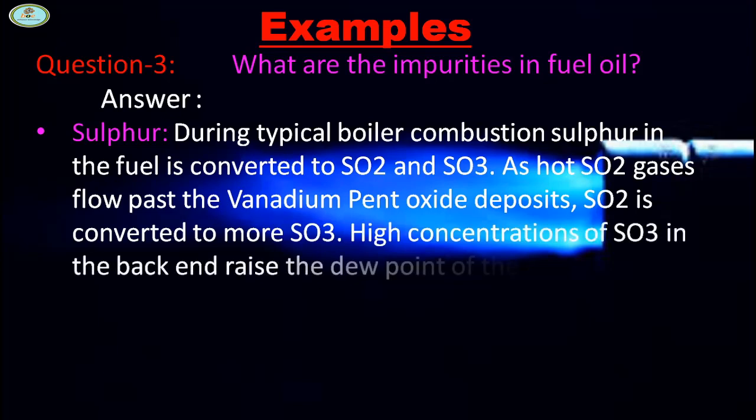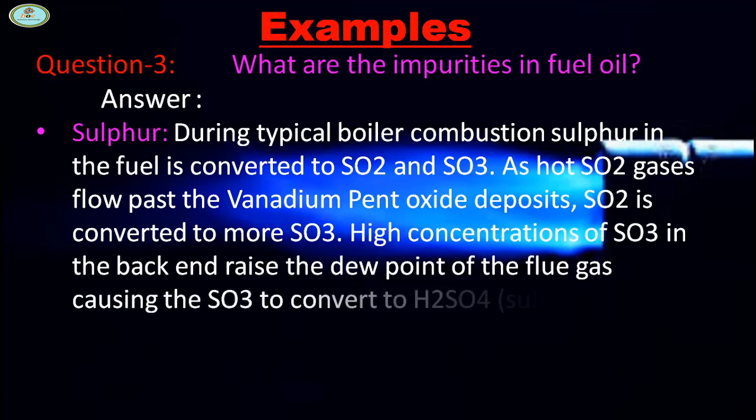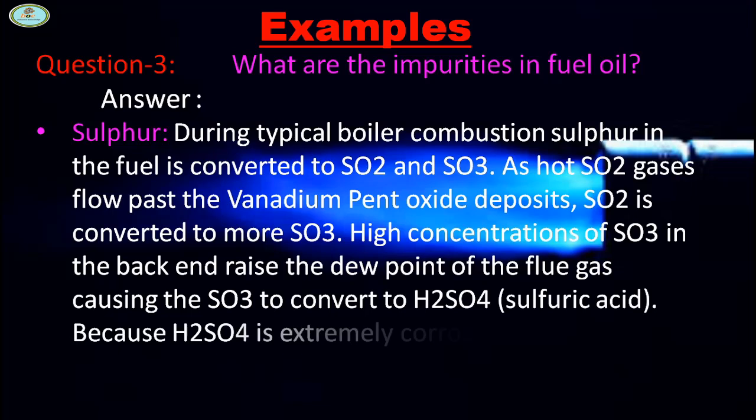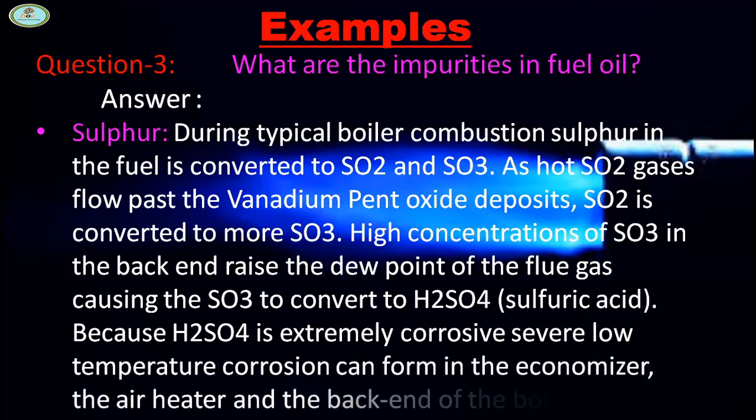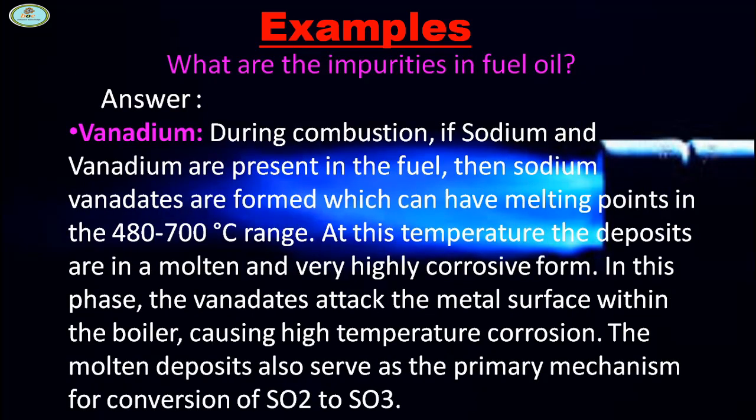As hot SO2 gases flow past vanadium pentoxide deposits, SO2 is converted to more SO3. High concentration of SO3 in the back end raises the dew point of the flue gas, causing SO3 to convert to H2SO4. Because H2SO4 is extremely corrosive, low temperature corrosion can form in the economizer, air heater, and back end of the boiler.